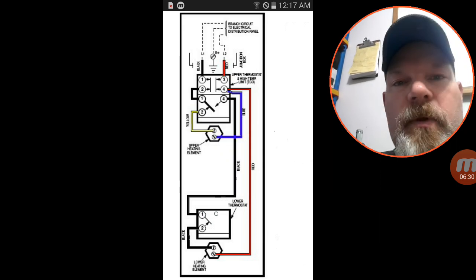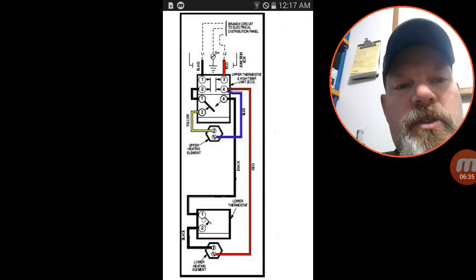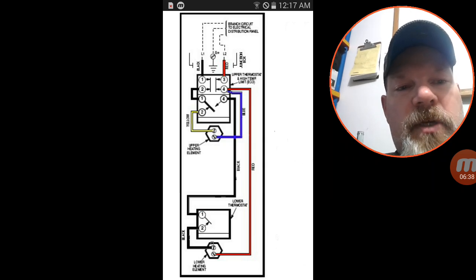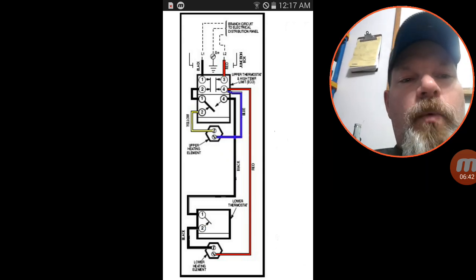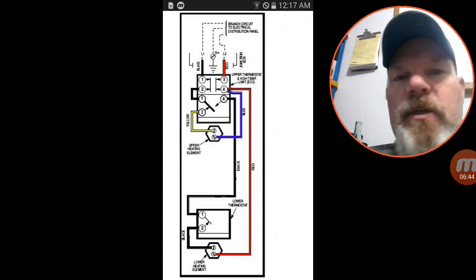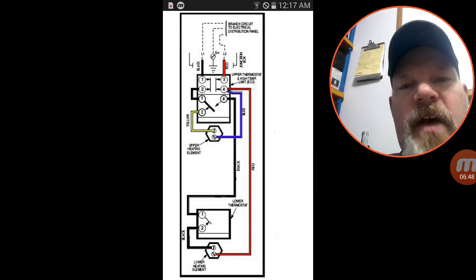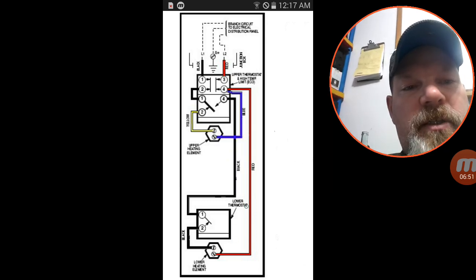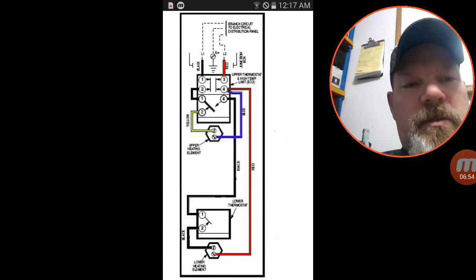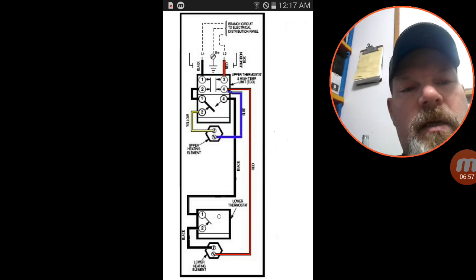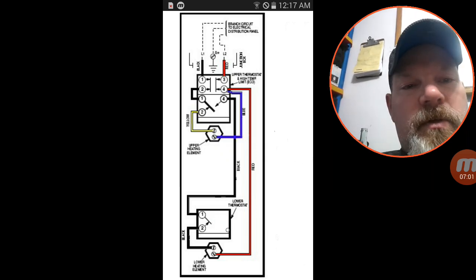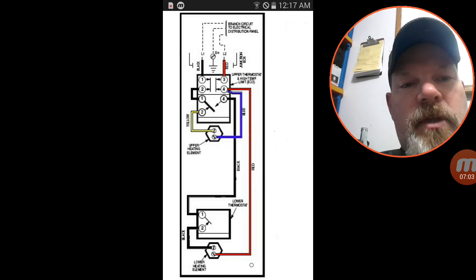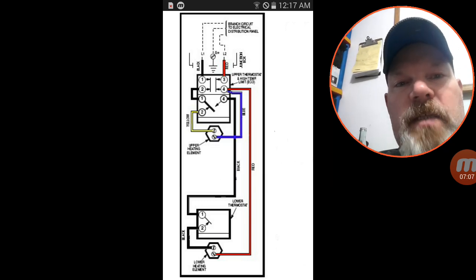Once it reaches a point to where the lower thermostat senses that drop in temperature, this switch closes, completes the circuit to this lower element. That will continue to operate until one of two things happens. Either it satisfies, so let's say you draw off hot water just enough to say do a load of laundry, maybe some dishes or something, you've drawn off a half a tank of hot water. That lower element will kick on and it will continue to be energized until this lower portion of the tank is satisfied for heat. Again, it shuts off and waits for the next time.